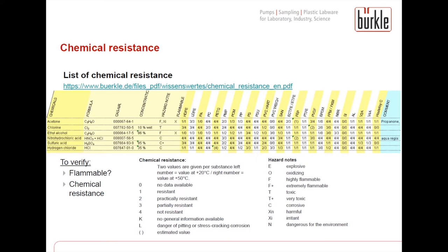One means very good resistance, two means still resistant, three means just partially resistant, and four means not resistant. We always recommend a pump when the material has a rating of 1/1 — perfectly resistant at room temperature and higher temperature — or also 1/2. All other combinations are not recommended.